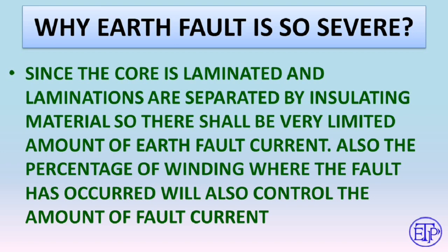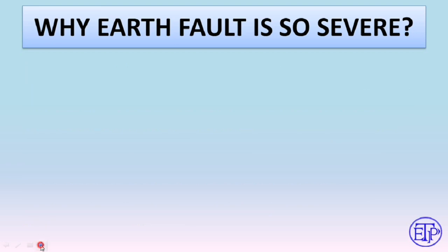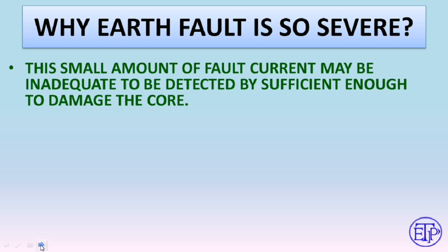This low earth fault current is dangerous because if insulation has failed and fault current passes through the core, the core carries current — but the core is not designed for carrying current, it is designed for carrying magnetic flux. So it can create hot spots and lose its magnetic property. This small amount of fault current may be inadequate to be detected but sufficient enough to damage the core. This is the major threat.